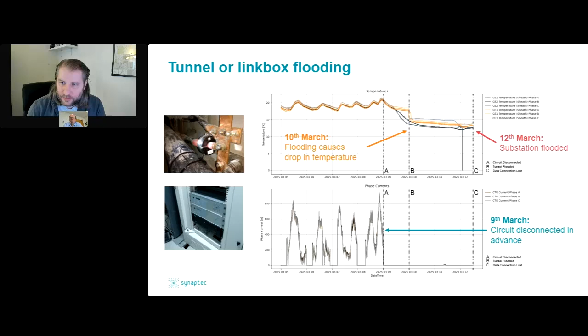Hopefully you can all see on the left-hand side of this picture that black circular device. This is a conventional current transformer, and we use conventional industry standard current transformers or voltage transformers, attaching our passive sensors to the secondaries, to the copper outputs from these devices. So it's completely passive. We're using a standard primary transformer, but how we're networking all of our sensors together makes for a very efficient system, because it can reach so many remote or inaccessible locations. By comparison, if you wanted to instrument a particular point along the cable for temperature, you would have to physically attach a fiber all the way along it.